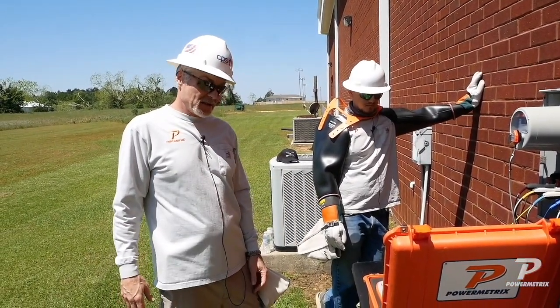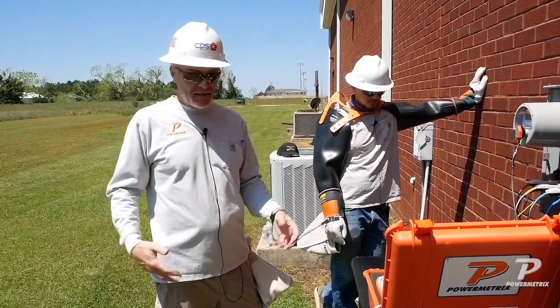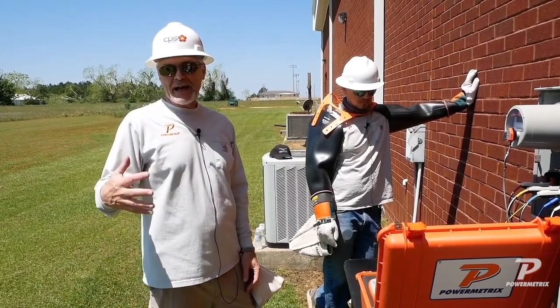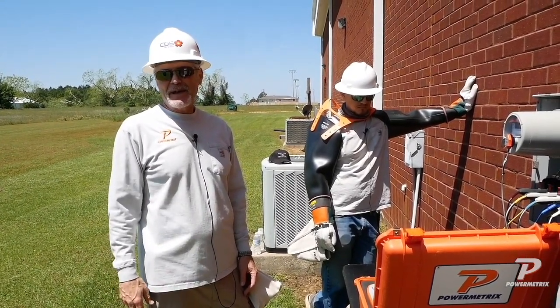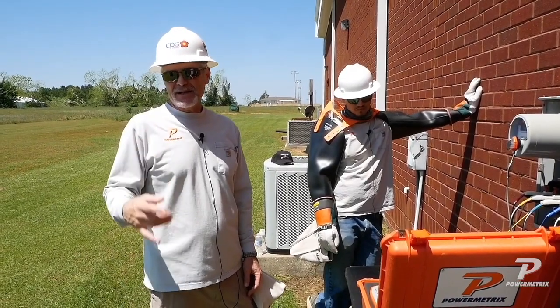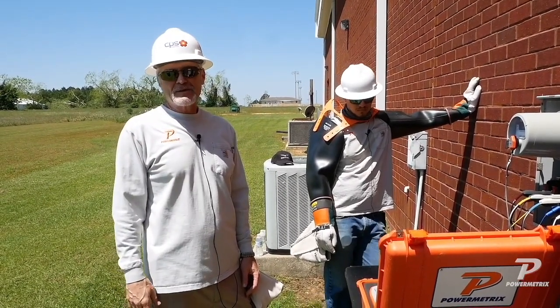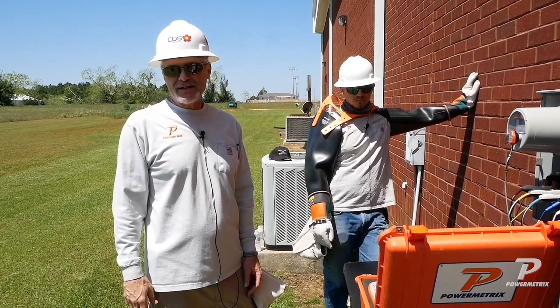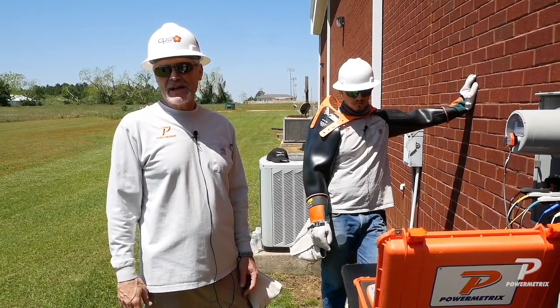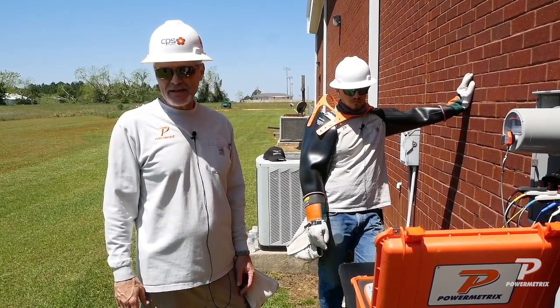It is consistently, we've traded out to make sure it wasn't one of these cables, but we're getting a high ratio error on B phase. A and C are testing fine. So right now, here is where I would want to take a look at that CT on B phase and maybe change that and see if that's not the issue.